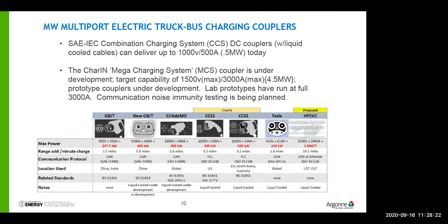CCS can deliver 1,000 volts at 500 amps, or half a megawatt, with a liquid cooled cable. The Megawatt Charging System is the next tier up, still a work in progress — basically an industry consortium designing the connector, which will then be adopted as a standard. Lab prototypes have shown you can run at 3,000 amps and maintain temperature stability. I lead the work group on communication noise immunity: what happens if I put a lot more noise in the connector? Does the system just shut down? Someone should test that — that's what we do in my lab.